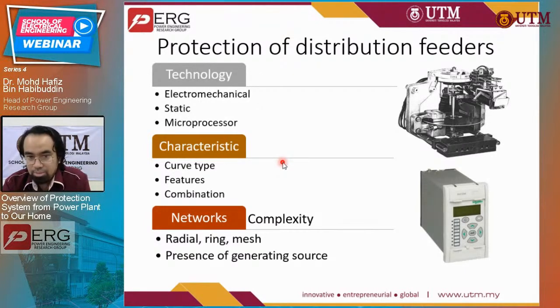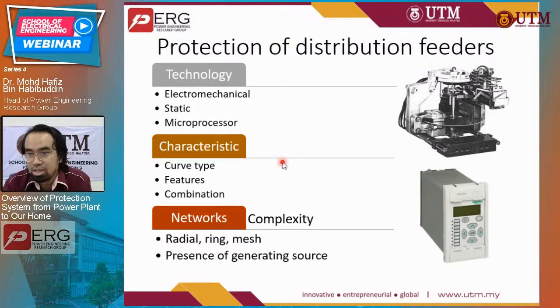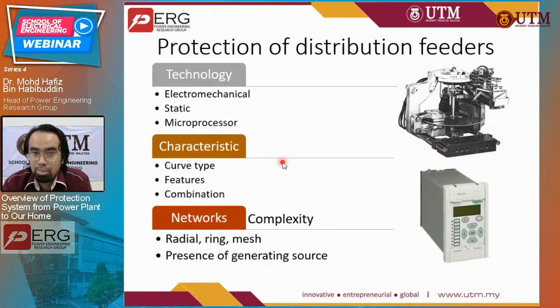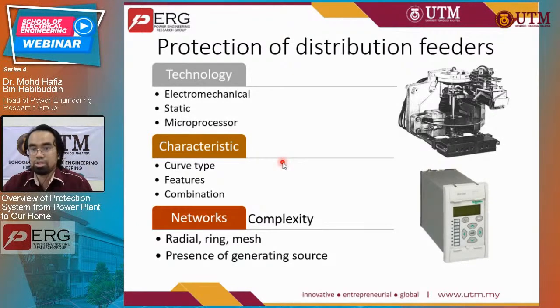Let's look at relay technology. Originally it was electromechanical — the characteristics are fixed based on the design, shape, and size of the relay. If you want to switch to a different characteristic, it's not possible with an electromechanical relay. But with the advancement of microprocessor-based relays, the characteristics and features of different relay types can all be inside one particular box — it's just a selection of characteristics, curve type, and features, all done in one single relay unit.